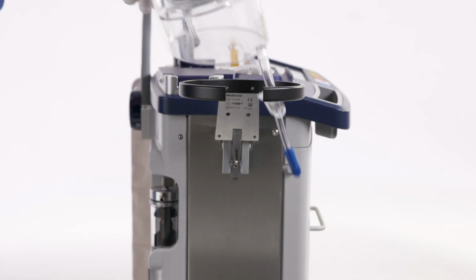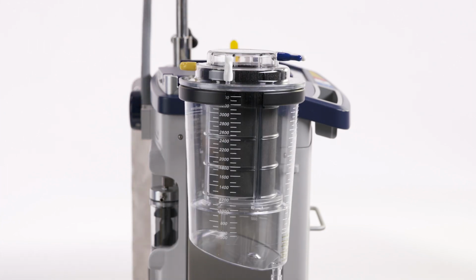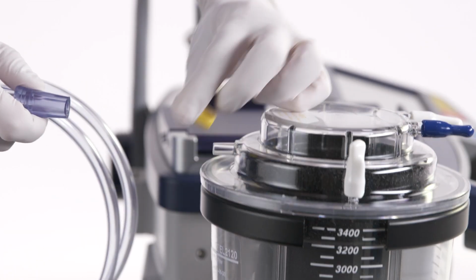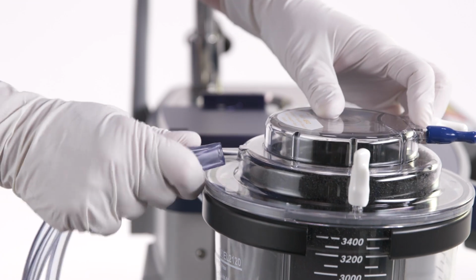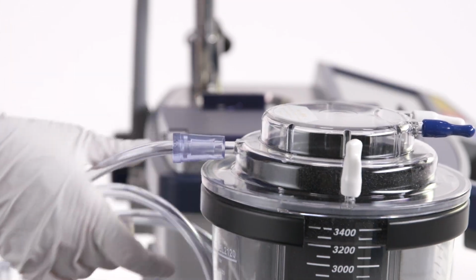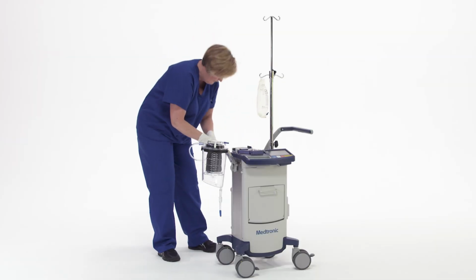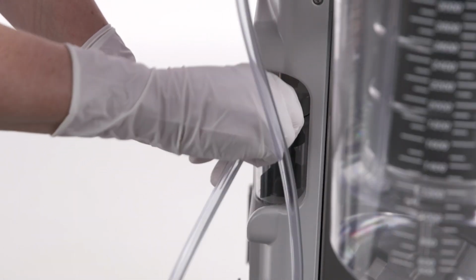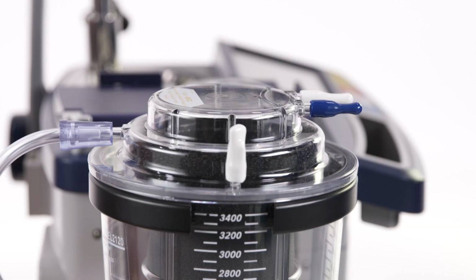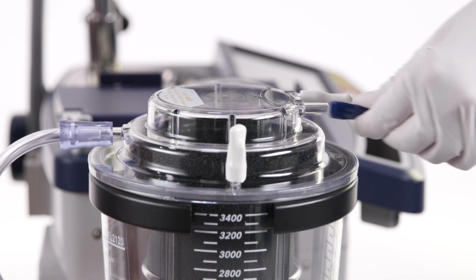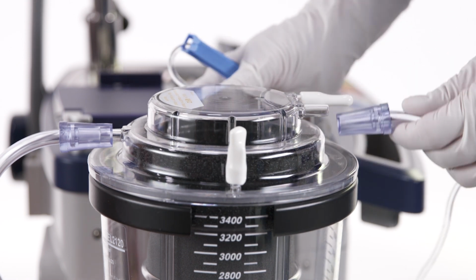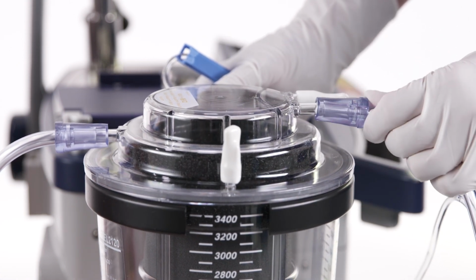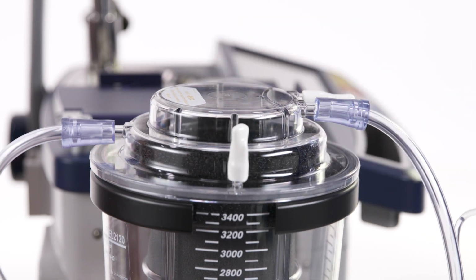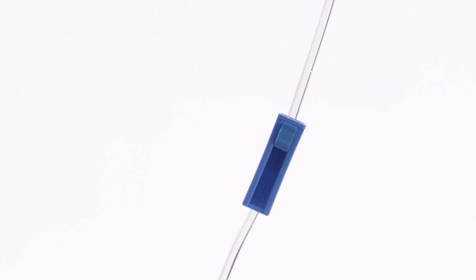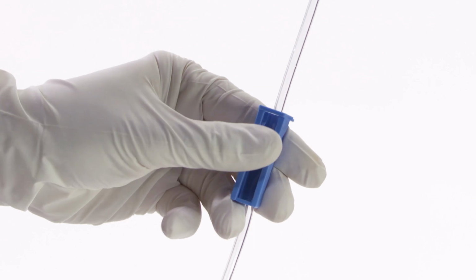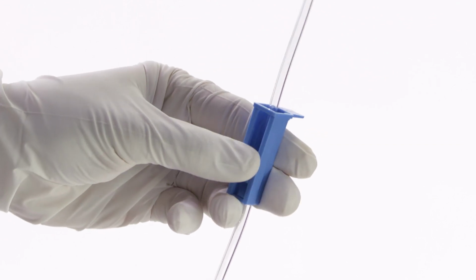Place the collection reservoir into the reservoir holder and attach a vacuum line to the yellow-capped port on the collection reservoir. Now attach the other end of the vacuum line to the vacuum overflow trap of the device. Attach the blue-capped suction anticoagulant line connector to either the blue-capped or white-capped inlet port on top of the collection reservoir. Close the roller clamp on the suction anticoagulant line.